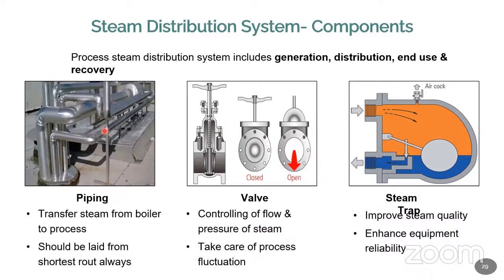We went to one industry in Bangalore. They are manufacturing turmeric powders. For that, they are using completely saturated dry steam, and they have multiple arrangements to take the water out of the steam. So you need a very proper cladding system, and that should have very pakka insulation. Mostly it is ceramic wool insulation, which surrounds the outer periphery of the pipe and is completely covered by aluminum cladding like this. At each and every point, you should always check the temperature at regular intervals.